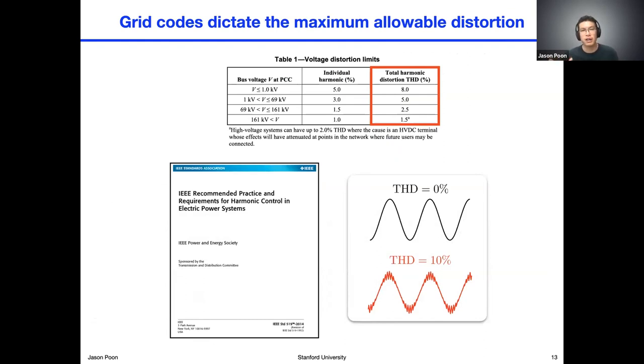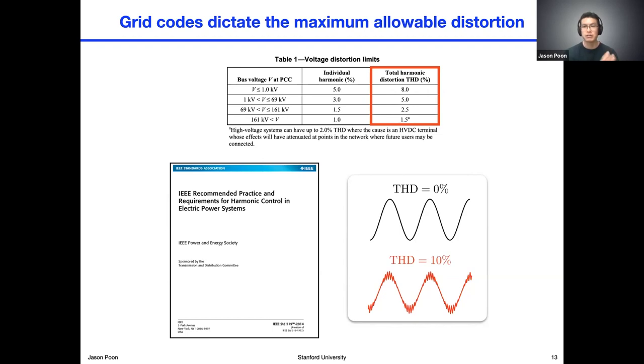There are grid codes that dictate the maximum allowable distortion that the utility will tolerate. A commonly used specification is IEEE 519 — the latest revision was from 2014. For these low voltage networks below 1,000 volts, the maximum allowable THD is 8%, which is already quite interesting in that we saw 8% THD can already cause some of these stability issues.